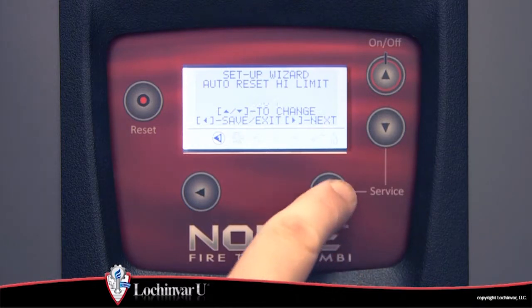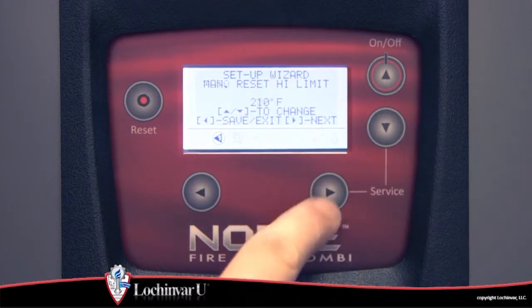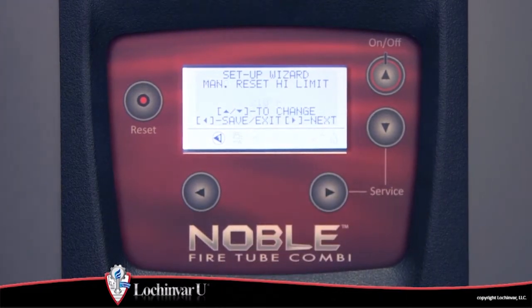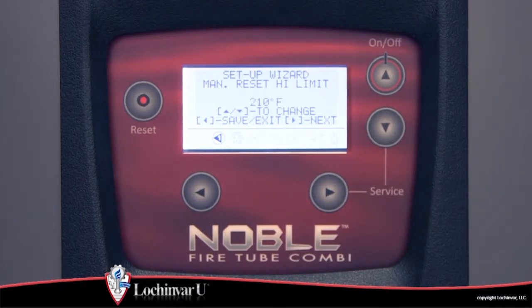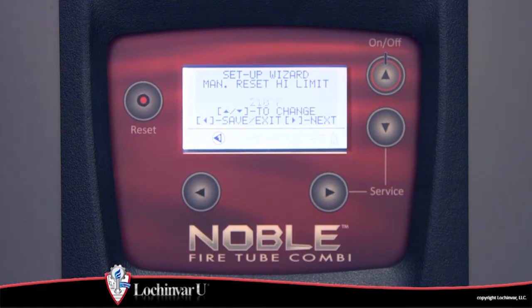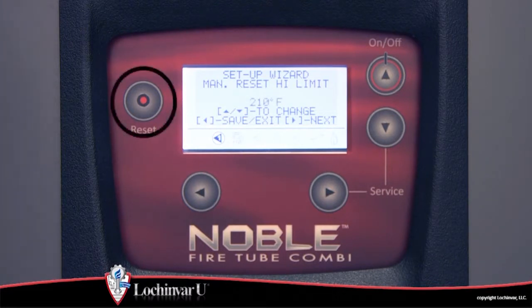The seventh parameter visible is manual reset high limit. When the outlet temperature exceeds the setting of the manual reset high limit parameter, the unit will shut down and remain in lockout until the reset button on the display has been pressed.